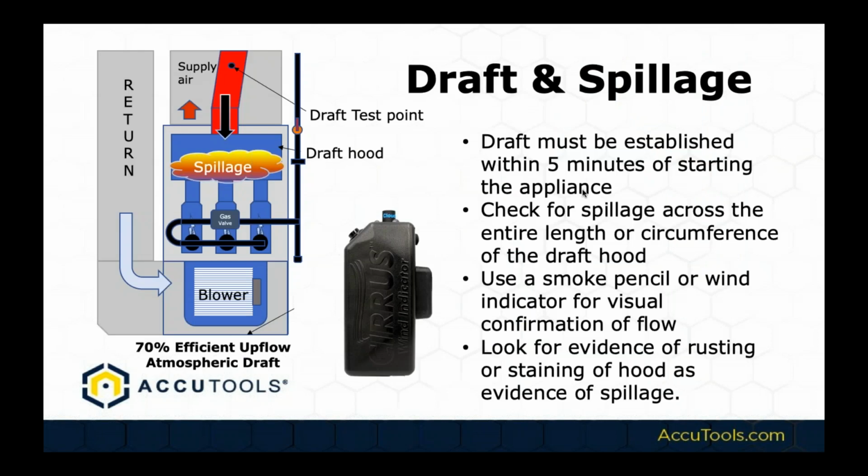Now, we do the same thing when we're testing this. A couple of important notes: draft doesn't always occur immediately because chimneys can be cold. If you've ever lit a fireplace, you know that sometimes you have to start a little piece of newspaper on fire to get the draft going. So we do have standards for draft. It must be established within 5 minutes of starting the appliance, which allows the chimney a little time to get warmed up. Then we check for spillage across the entire length or circumference of the draft hood, and we'll use a smoke pencil or wind indicator.